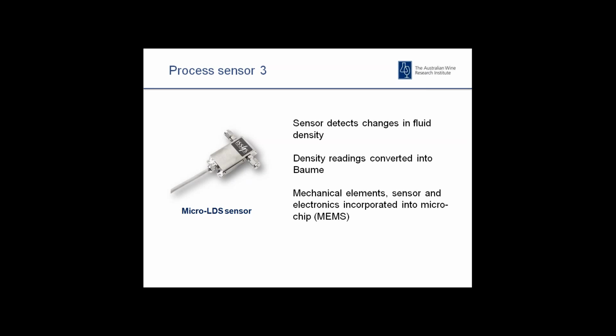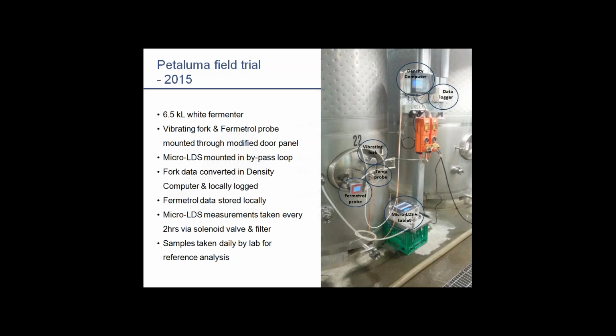And I'll show you in a minute. In this particular application, we looked at a bypass loop to utilize this sensor rather than going into the ferment vessel itself. So this is the trial setup at Petaluma in 2015. So we've got a 6.5 kiloliter white fermenter. We've got the Fermetrol and the vibrating fork, which were inserted through a modified door panel. We've got a localized temperature probe here to provide temperature adjustment for the density measurement. That's done automatically on the Fermetrol probe or within that unit.